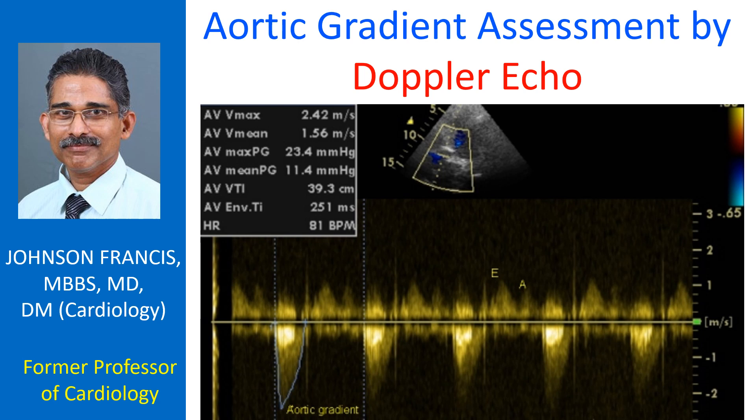Hence, the Nyquist limit will be low for conventional pulsed Doppler with low pulse repetition frequency, and high for high pulse repetition pulsed Doppler. Theoretically, it is infinite for continuous wave Doppler.